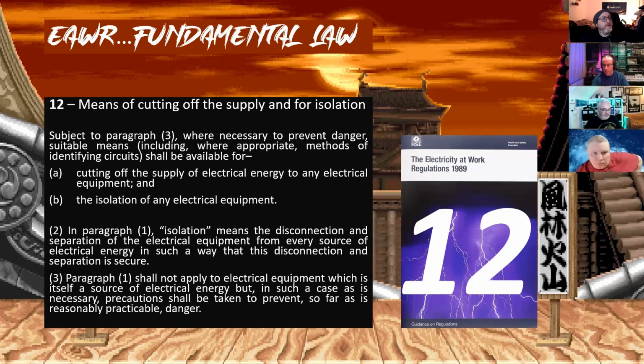Subject to paragraph 3: when necessary to prevent danger, suitable means, including where appropriate methods of identifying a circuit, will be available for cutting off supply of electrical energy to any electrical equipment and isolation of any electrical equipment. In the first paragraph, isolation means disconnection and separation of the electrical equipment from every source of energy in such a way that this disconnection and separation is secure. And to the first paragraph, it shall not apply to electrical equipment which is itself a source of energy, but in such a case as is necessary, precautions will be taken to prevent, so far as reasonably practicable, danger.